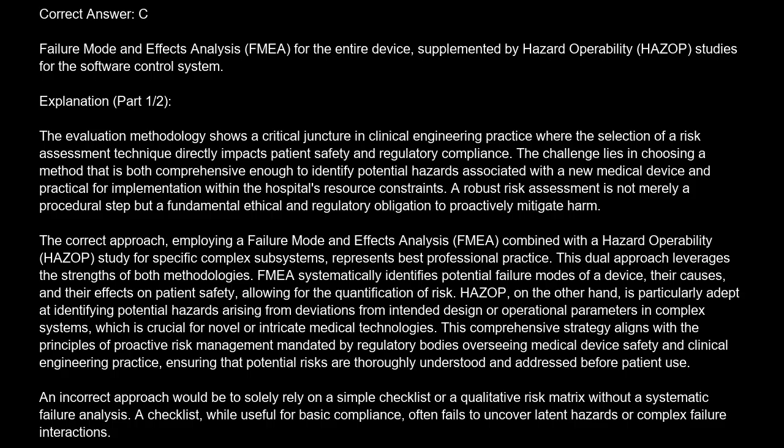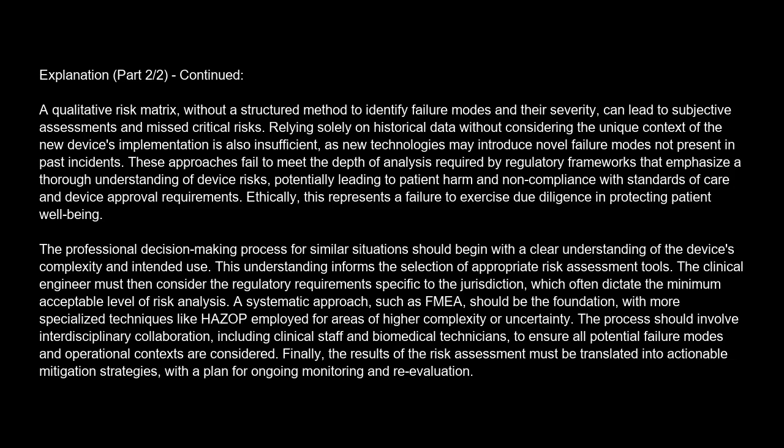An incorrect approach would be to solely rely on a simple checklist or a qualitative risk matrix without a systematic failure analysis. A checklist, while useful for basic compliance, often fails to uncover latent hazards or complex failure interactions. A qualitative risk matrix, without a structured method to identify failure modes and their severity, can lead to subjective assessments and missed critical risks. Relying solely on historical data without considering the unique context of the new device's implementation is also insufficient, as new technologies may introduce novel failure modes not present in past incidents.